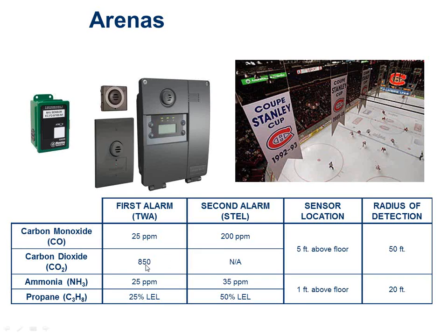We're showing 850 parts per million as a control point on here. Typically, we have a linear control ramping scale that goes with the outside ventilation damper. So I'll typically be ramping the ventilation between, say, 600 parts per million and 1100 parts per million. So 850 we put on the screen here just as a number to put up there. It's kind of a gauge figure in your head. I might have carbon monoxide, depending on what kind of Zamboni I am driving, or I might have propane, depending on what kind of Zamboni I am driving, right?